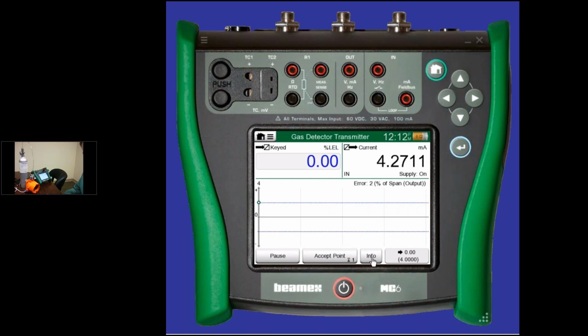And I'll go ahead and accept this pair of readings. And now it's telling me to move to the mid-range here. So my target is 50, my expected output would be 12. So I'm going to go to my regulator here and open this guy up, and you'll see the milliamps start to move. And remember, it said I should wait 60 seconds.